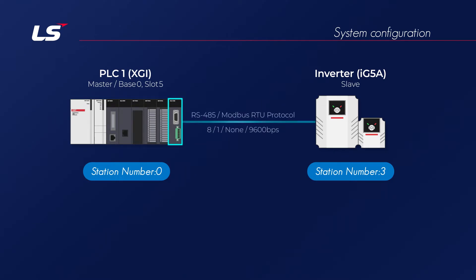The basic parameter settings in PLC drive communication are as follows: Modbus RTU protocol, data bit 8, stop bit 1, parity bit none, communication speed 9600 bps.